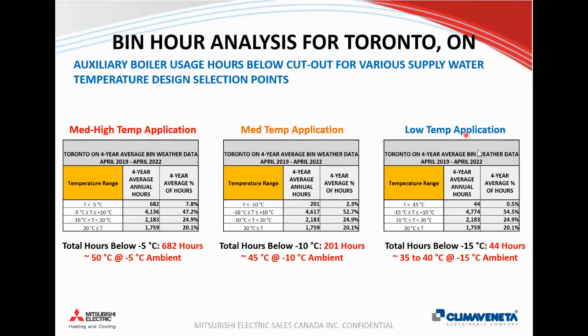And if you're looking at a low temperature water application, so low temperature heat emitters, perhaps cascade systems where you have a central plant reversible heat pump supplying very low grade hot water to be an input to the evaporator side of another heat pump, either a large scale central heat pump or in-suite water source heat pumps that transfer energy to the air. There are different applications, and radiant in floor, of course, as well. So if you are able to design with a 35-degree temperature, we're basically covering off 99.5% of the year and running auxiliary below -15 for about 44 hours.